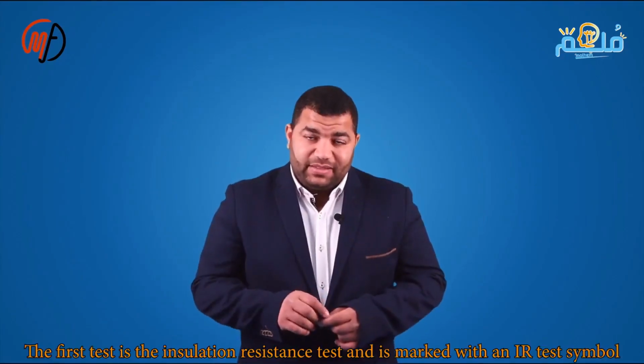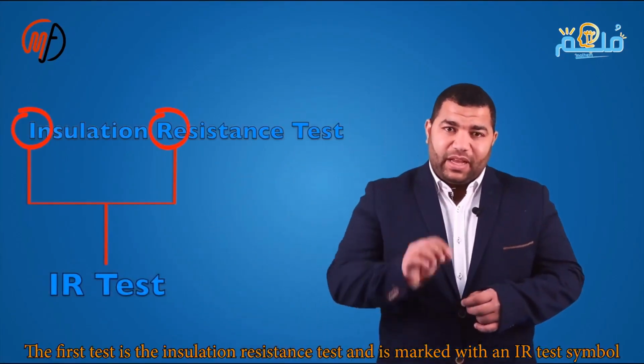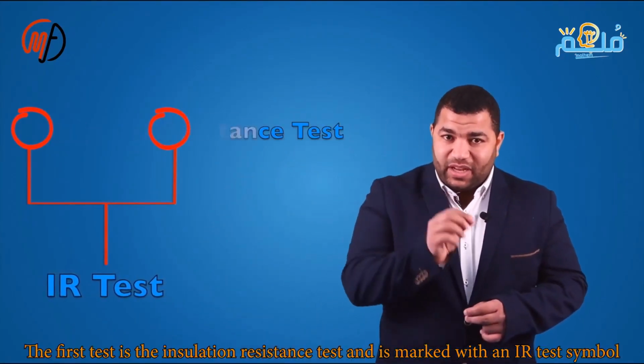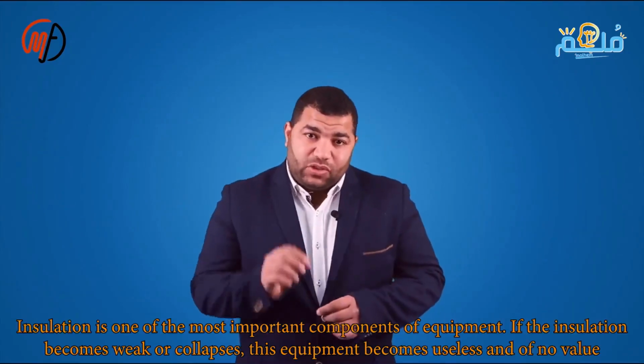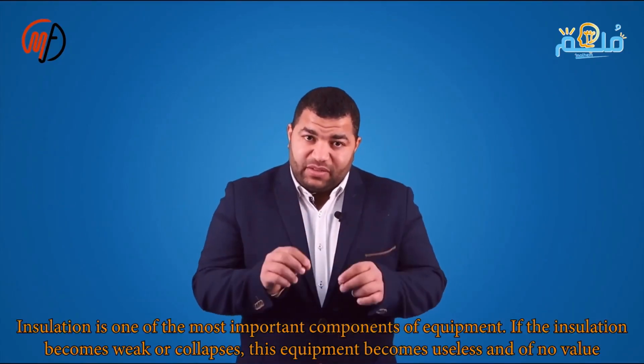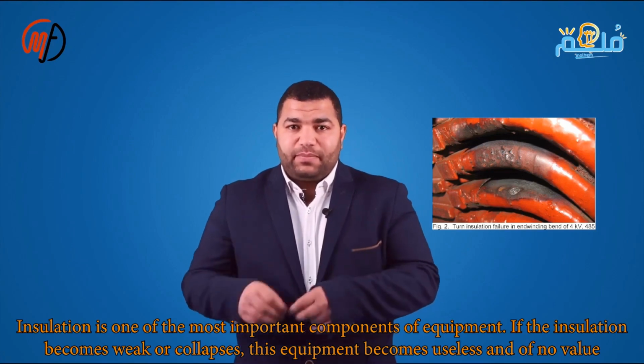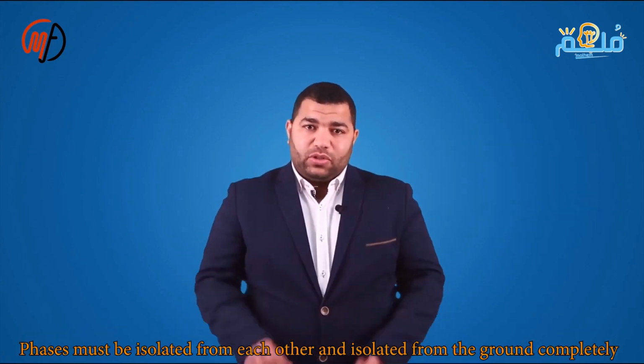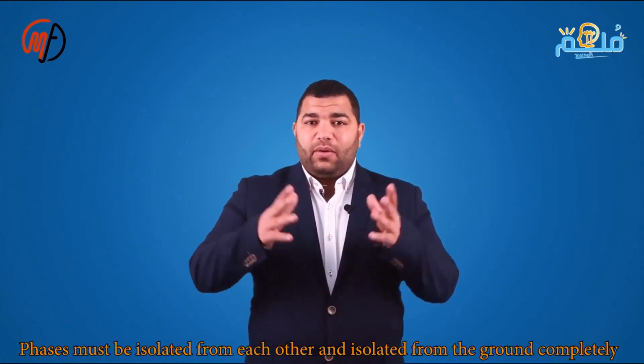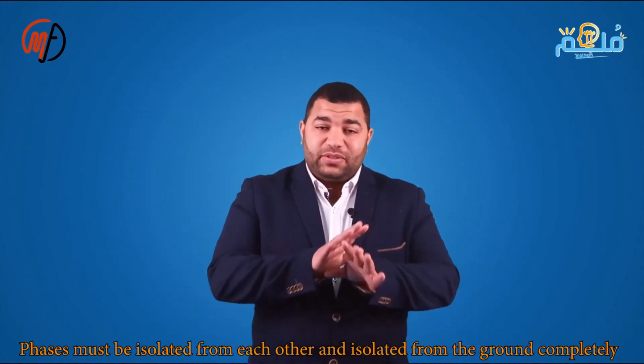The first test is the insulation resistance test. Insulation is crucial for equipment. If the insulation weakens or fails, this equipment is useless. The phases must be insulated from each other and the ground to avoid faults, as short circuits occur from phase connections or to ground. Due to insulation's importance, we list resistance tests.